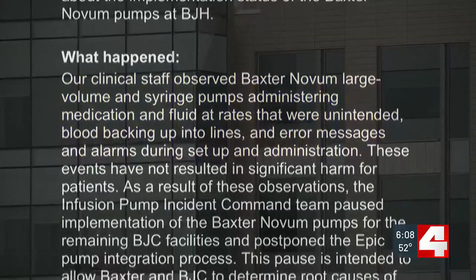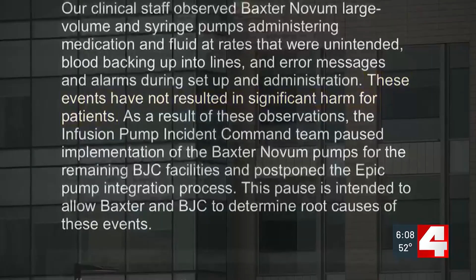An email sent recently on March 28th to staff there and obtained by us Tuesday says, quote, our clinical staff observed Baxter Novum pumps administering medication and fluid at rates that were unintended, blood backing up into lines, and error messages and alarms during setup and administration. The email to West County staff says, quote, these events have not resulted in significant harm to patients, but says further rollout is on pause, saying, quote, this pause is intended to allow Baxter and BJC to determine the root causes of these events. It encourages staff to continue reporting any concerns or events.